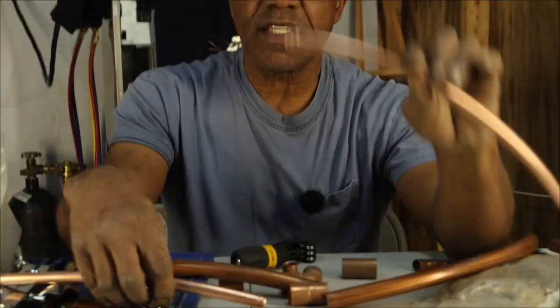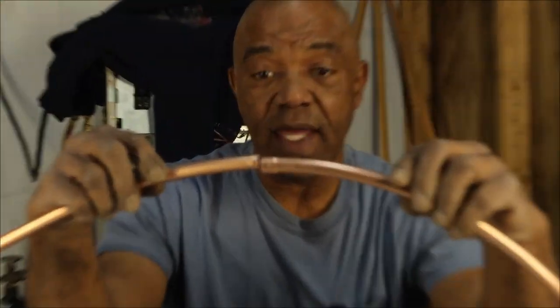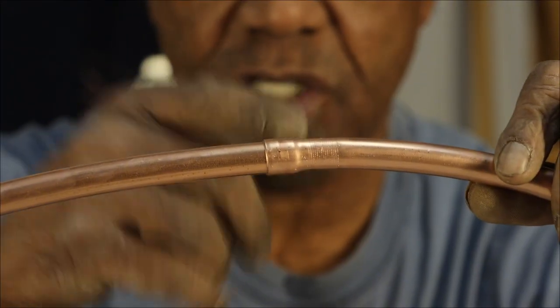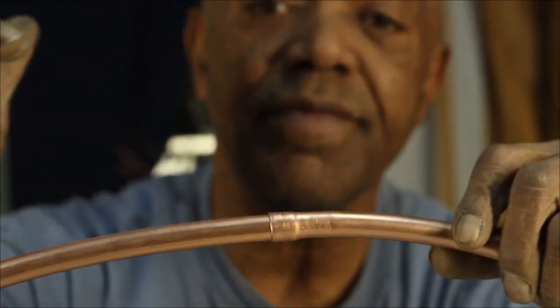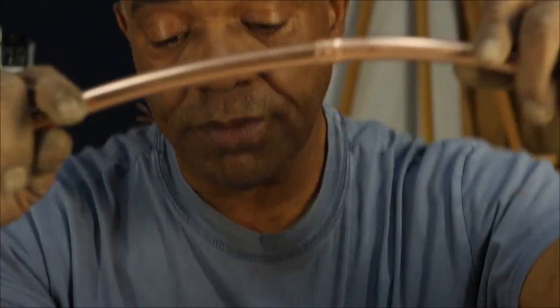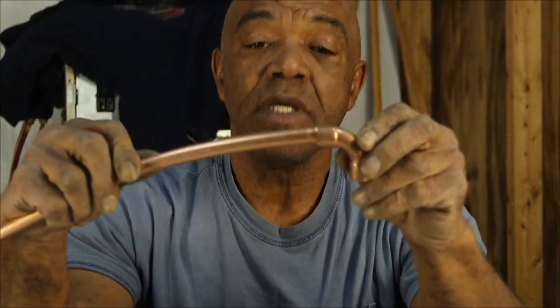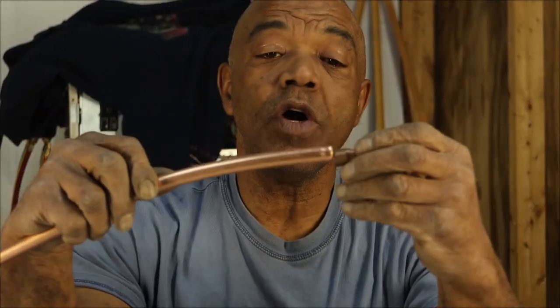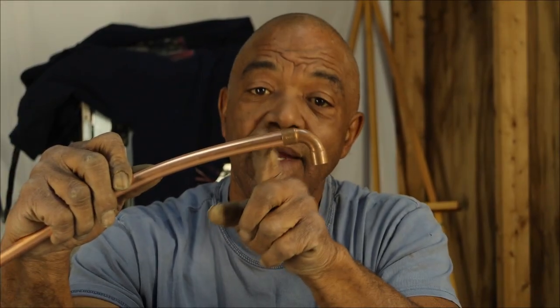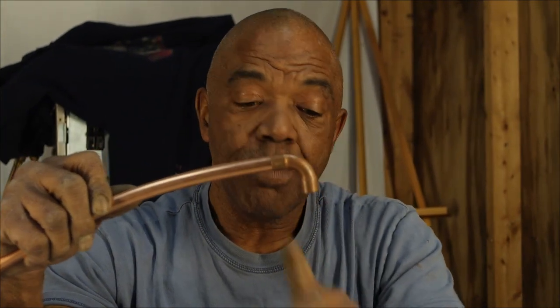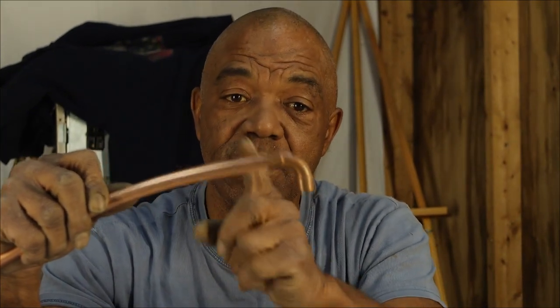But if I swedge the copper and then I connect it, I only have one braze connection, limiting the amount of leaks that I could have. Now, I could use an elbow on this copper. I do have the right size elbow. I could use this elbow to turn, but again, now I have two braze connections, one at this end and one at the copper going in this end.